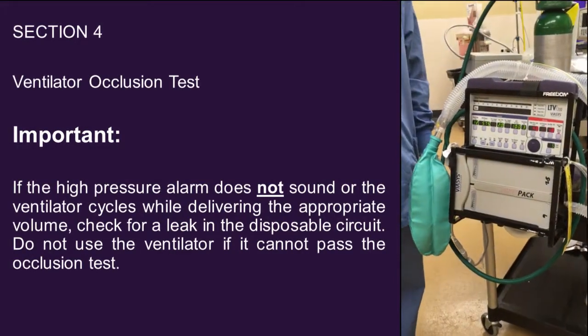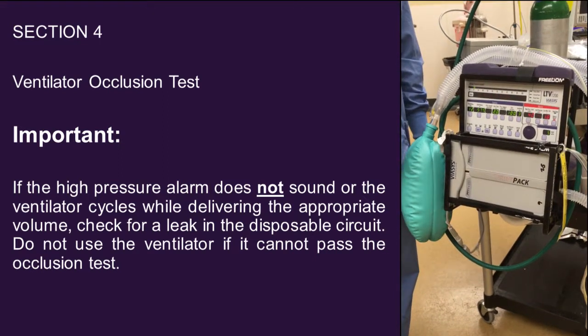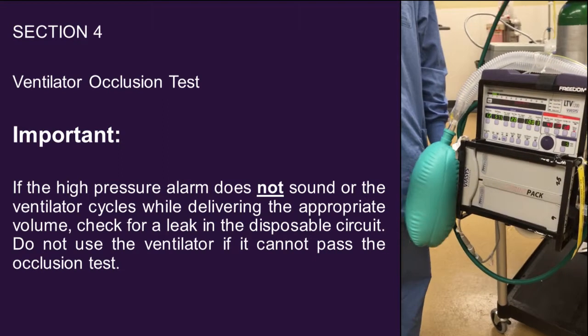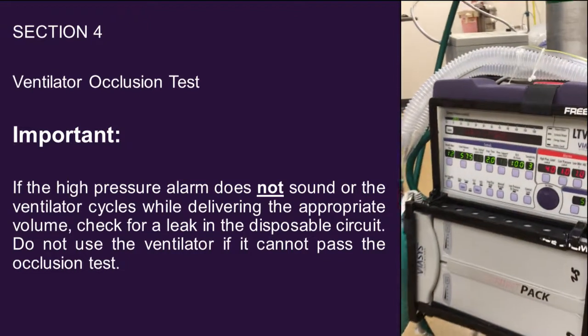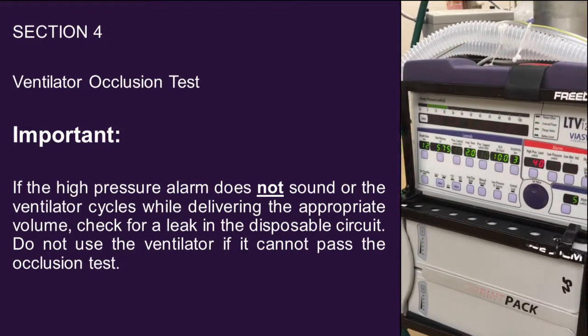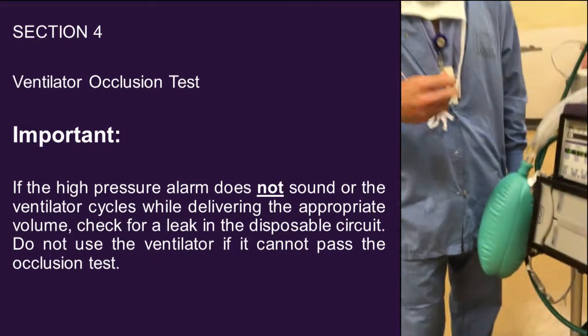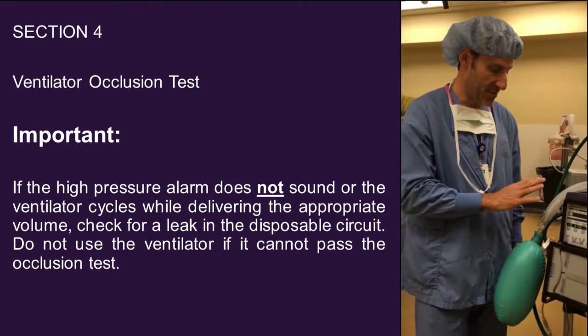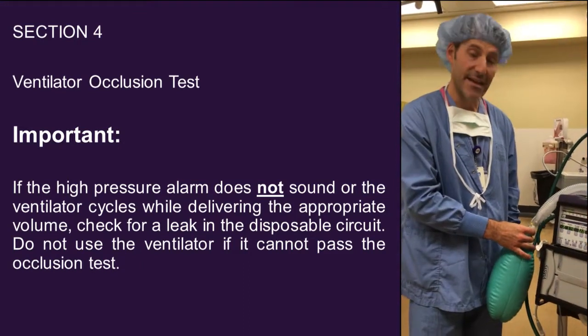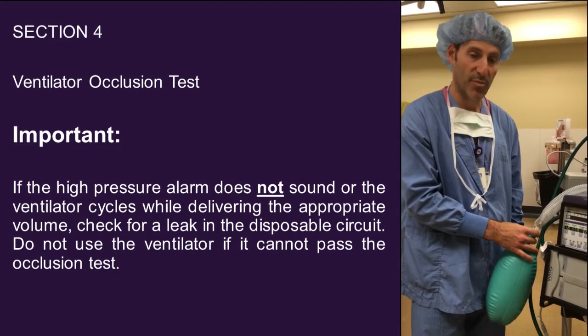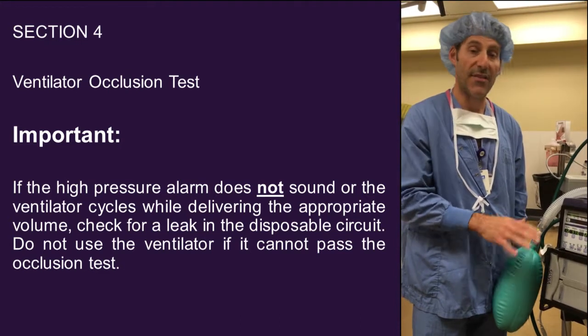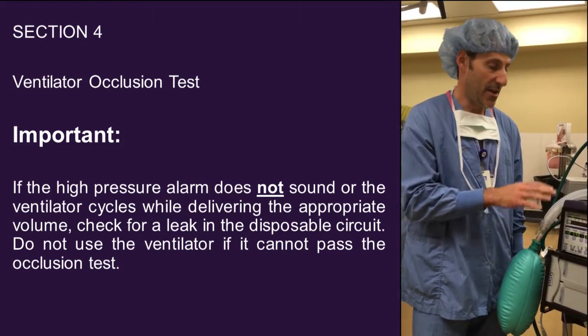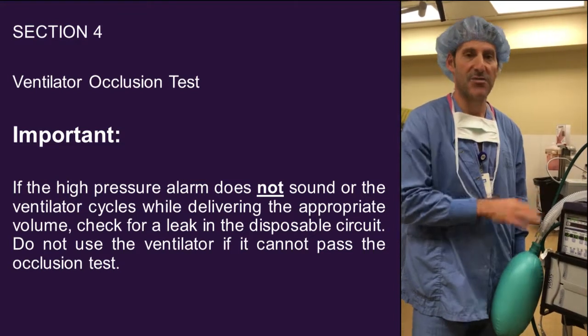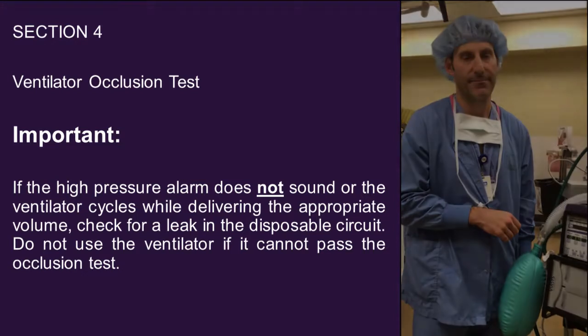If the occlusion test is performed and the ventilator does not alarm or cycles while delivering the appropriate volume, you should go through the troubleshooting process to determine whether or not there's a leak anywhere within the circuit that you placed on the machine, or whether or not there is a problem with the machine itself. And until that is figured out, you should not be using that ventilator to transport the patient.